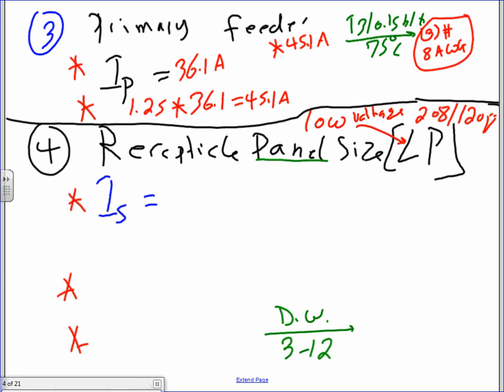Now, Adam, we sized the primary. We sized the transformer. We sized the primary overcurrent device. And we sized the feeder. Next, we need to size the secondary conductor, or the secondary panel. Number 4 is the panel. You're going to take the 30 kVA, the same 30, divided by 1.73 times the voltage on the secondary side, 208. If you do your math, you should come up with the same number, 83.3 amps.